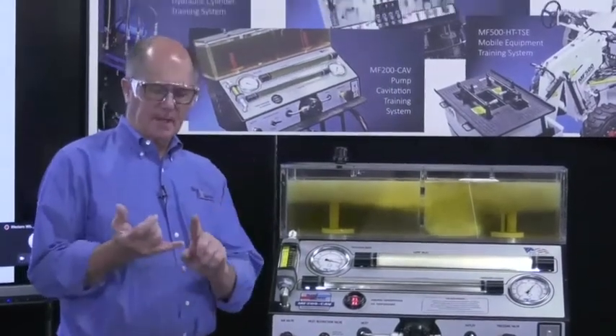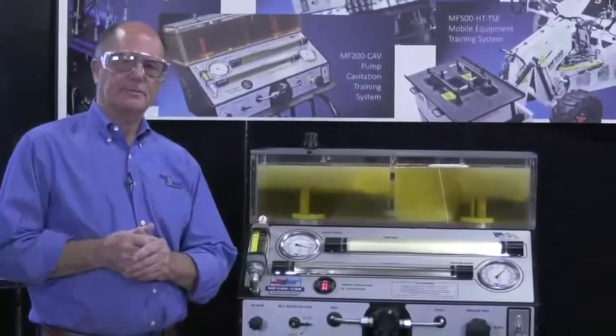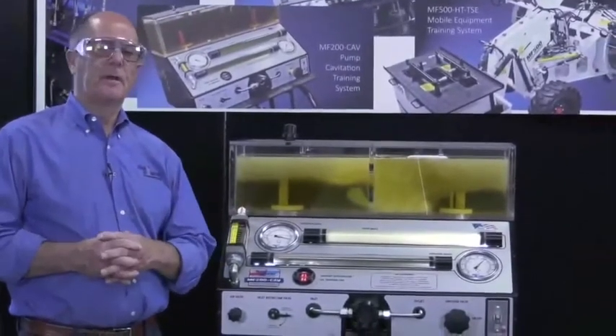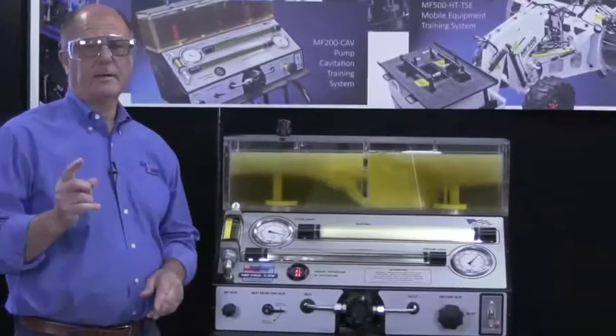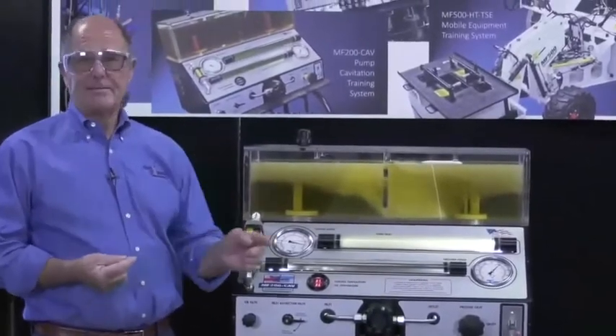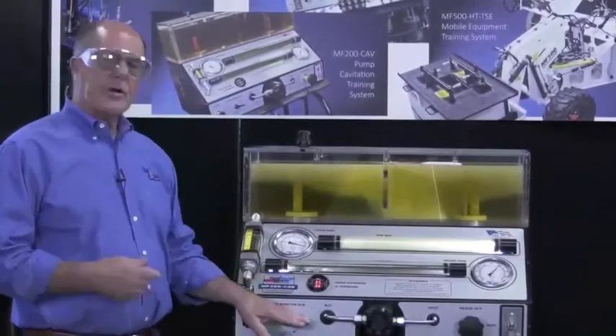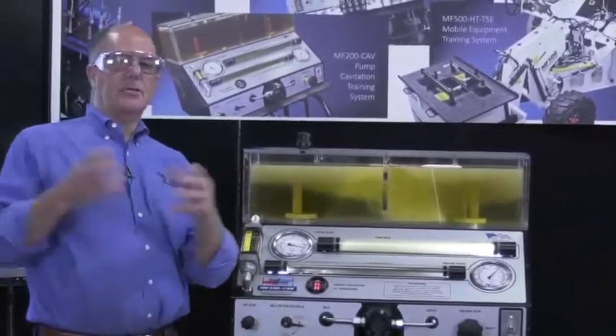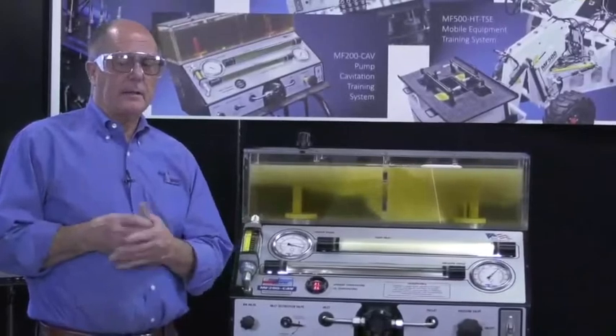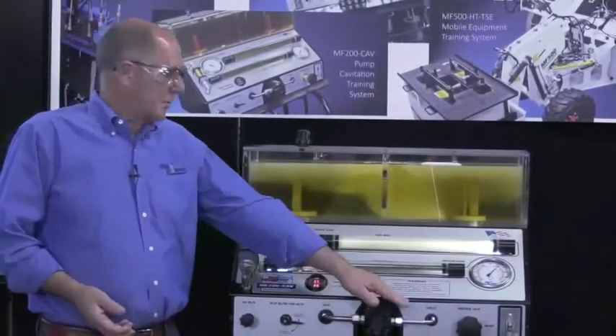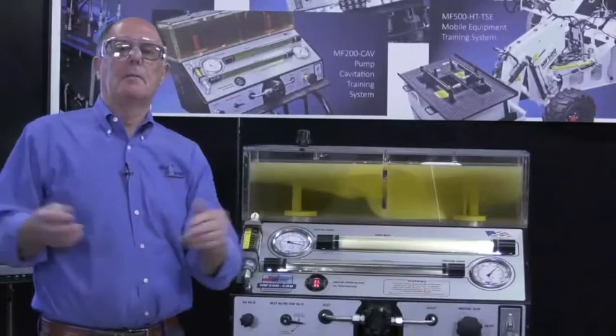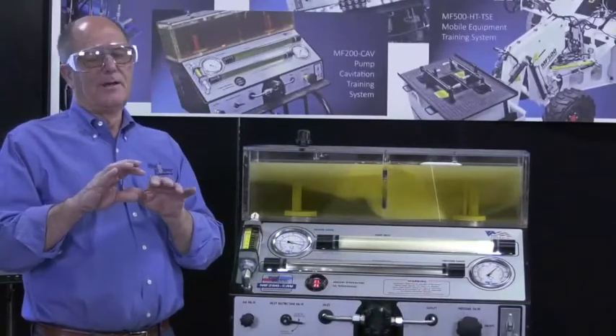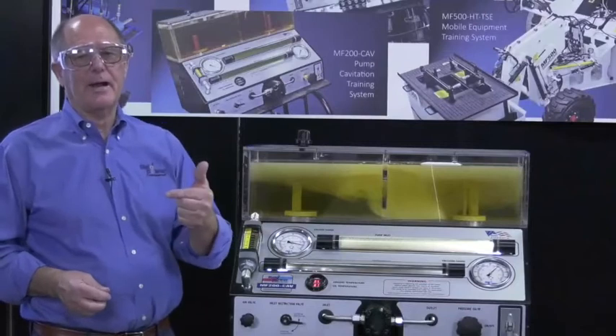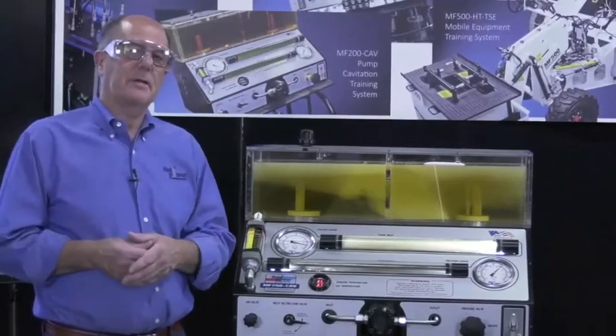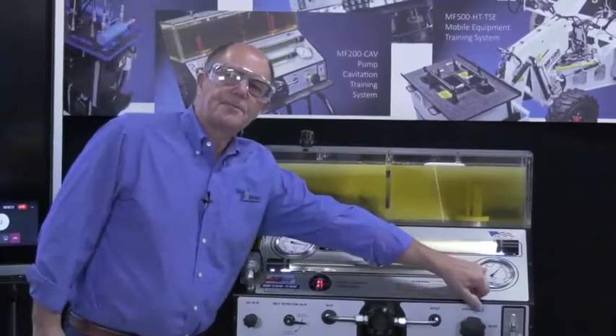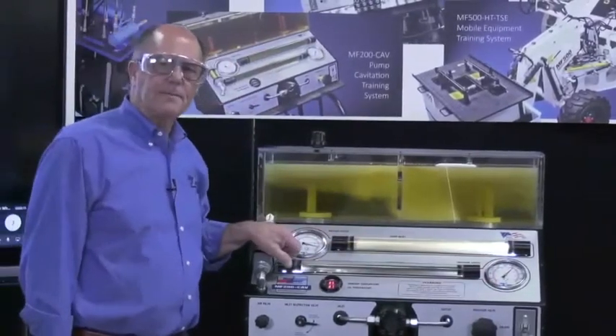Cavitation. Let me do a summary. First of all, we got to know the patient. Everything was normal. Our inlet restriction was 4 inches of mercury. Second, we simulated cavitation. I restricted the flow going into the pump, allowed the dissolved air to come out of the oil, and I had cavitation, which was localized to the pump. As soon as the oil came out the other side of the pump, the problem disappeared. I'm not saying we don't have a problem because pieces are going down line. I'm just saying there's no evidence of cavitation. I did lose pressure and I did lose flow.